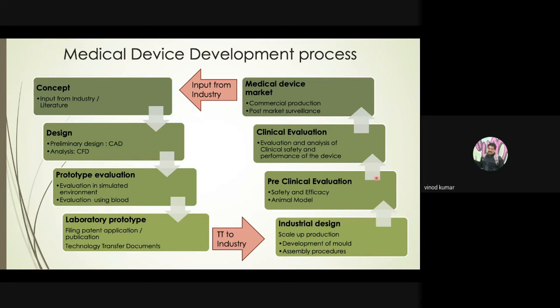Then there is a stage called preclinical evaluation, where the medical device... Clinical stages means you are reaching the clinic or the hospital. So the preclinical evaluation phase is a phase where you are doing a lot of experiments to ensure that the device is safe to use on human subjects, and that it has the efficacy which we intend from the device. So basically, you're trying to prove the safety and efficacy of the device in the preclinical evaluation phase. This is normally done with the help of animals also. We may do experiments on animals depending on the situation.